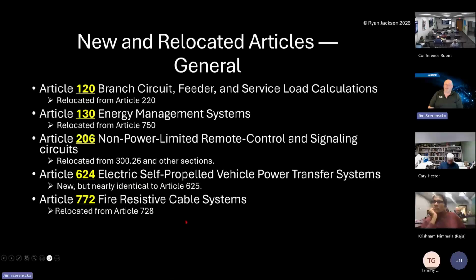So some of the articles were relocated. All of you, I'm sure, especially engineers, are used to using Article 220 for sizing a service, right? Whether you use the optional or the standard method, how many amps per linear foot for show window lighting or multi-outlet assemblies, or whatever the case may be. And it's always been 220, right? 220 dot this, 220 dot that. 220.12 gives you the demand, how many volt amps per square foot for an assembly. 220.42, or whatever it is, the tables.